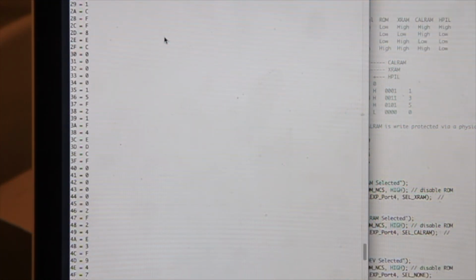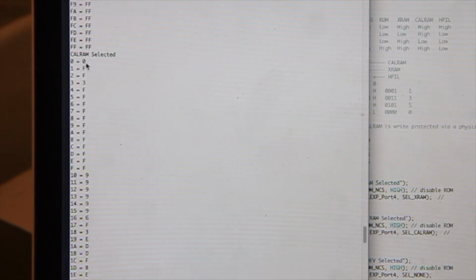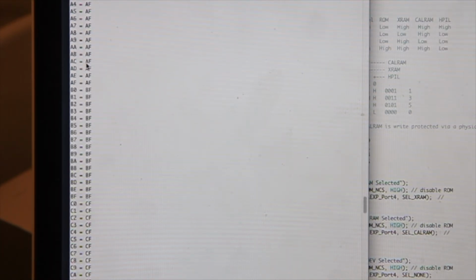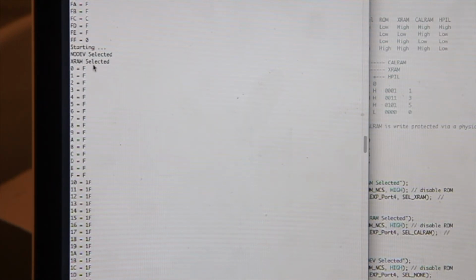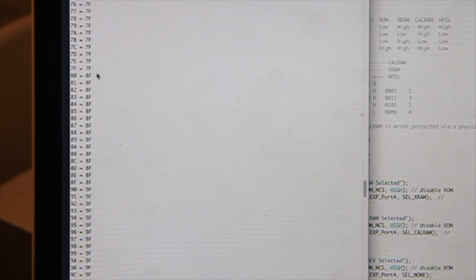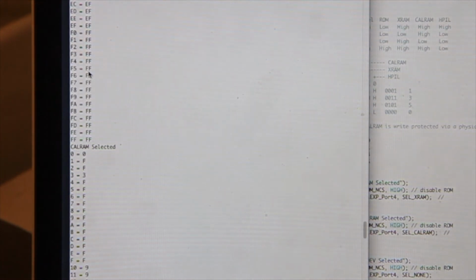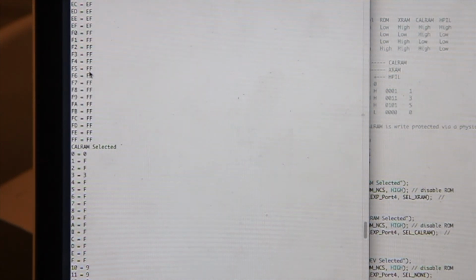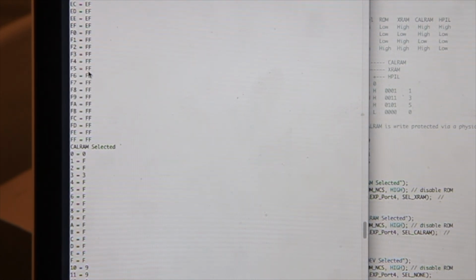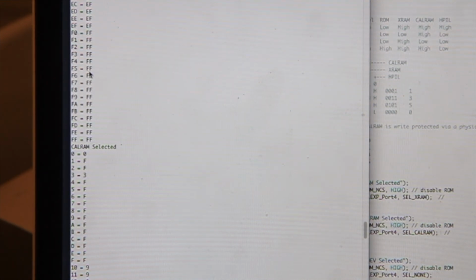This particular test is printing the contents of the calibration RAM, and it is running a read-write test on the XRAM, and this is where we see that while the least significant 4 bits are always F, the most significant actually track the address. So essentially I'm writing the address to the position, so I can see that the high order bits track the address, while the least significant bits don't. So one of the two XRAM chips is not working, and once I replace it, I will be able to continue testing. Thank you.